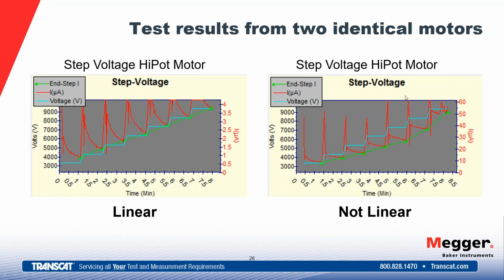Here on the right, we see that we do have a linear response all the way through the fourth point. And we start getting slight nonlinearity and then a bigger jump here. And then at our final test voltage, we get an even bigger jump in current. As we increase voltage, our current should respond in the same way. But on those latter steps, as we increased our voltage, our current increased more in the next step. This is an indication of insulation weakness.